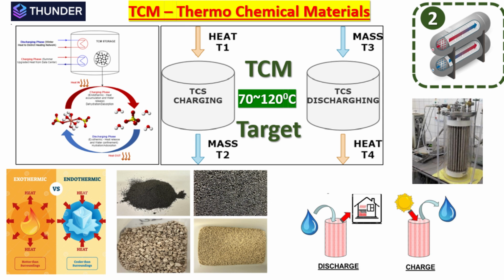Our Italian partner, HiRef, specializes in refrigeration technologies and heat pumps. We need to develop a low cost, environmentally friendly mechanical heat pump system to take 30-40 degree C water and bump it up to 120. Current heat pumps go up to 70, and conventional propane-based ones maybe 75-80. CO2 heat pumps can reach high temperatures but are very expensive. So we're trying to develop cost-effective, practical HFO-based refrigerant heat pump systems to achieve 120 degrees C.